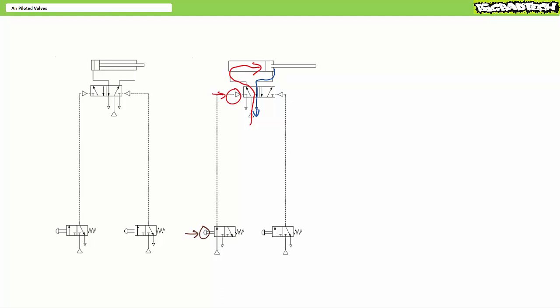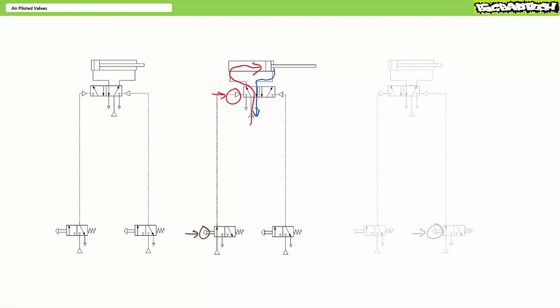The same can be said for retraction. When an operator releases push button one and presses push button two on the right hand side, it sends a tiny puff of air to the air pilot on the right hand side, shifting the valve into a position such that pressurized input port one is routed to actuator port two and actuator port four is vented to exhaust port five. As with extension, given negligible losses in the short primary lines, the cylinder retracts with undiminished strength and speed.